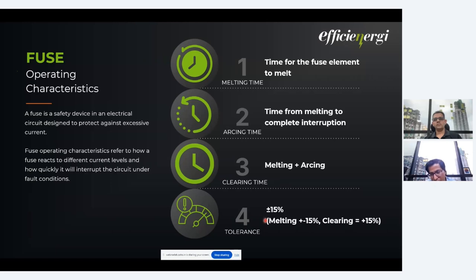Then there is one more important aspect of the TCC, which is tolerances. In a fuse we can have plus or minus 15% tolerance. Again, plus or minus 15% in melting and plus 15% in clearing. We have a separate slide for tolerances, so in that section I'll explain it in more detail.